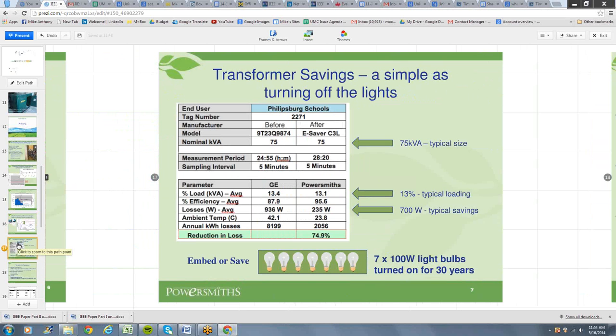So this is an example of a typical savings scenario for a 75 kVA, which is one of those average size transformers which you see in buildings. You've got before and after. What you've got here, as you can see, 75 kVA. We go down to the loading line, which is the next bullet there. We're around 13% loading on average. You look at the gap in losses. The before transformer, 936 watts. After, down to 235. So about 700 watts of savings.